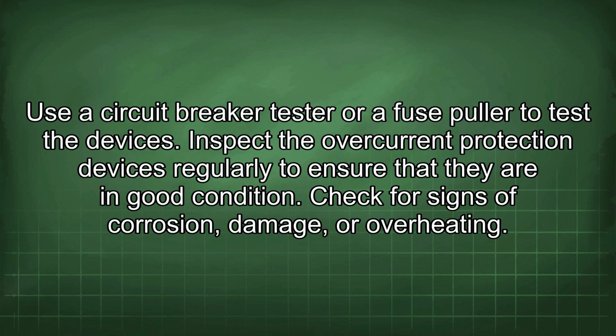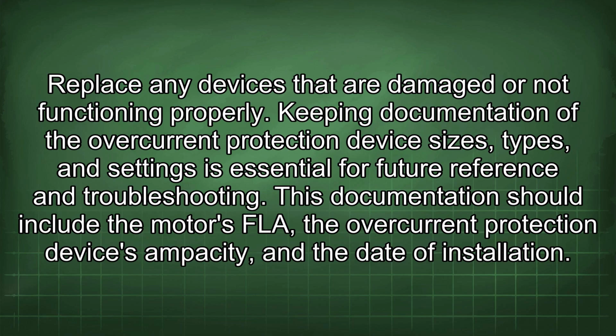Inspect the overcurrent protection devices regularly to ensure that they are in good condition. Check for signs of corrosion, damage, or overheating. Replace any devices that are damaged or not functioning properly. Keeping documentation of the overcurrent protection device sizes, types, and settings is essential for future reference and troubleshooting. This documentation should include the motor's FLA, the overcurrent protection device's ampacity, and the date of installation.